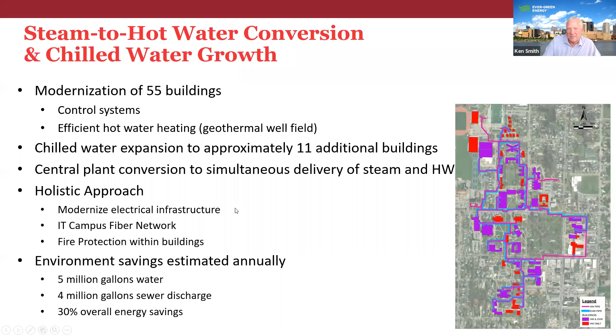In this case, the heat pumps are utilizing the geothermal well, and the temperature is very constant in the geothermal well. So you're lifting the source energy from around 55 degrees. Actually, as you start to utilize the geothermal wells, you're putting energy in that you're storing. When you're in cooling mode, you're storing heat and you're going to recover that heat later on. So you're not operating it from outdoor air temperature, you're operating it from the energy you've already stored down in the earth.